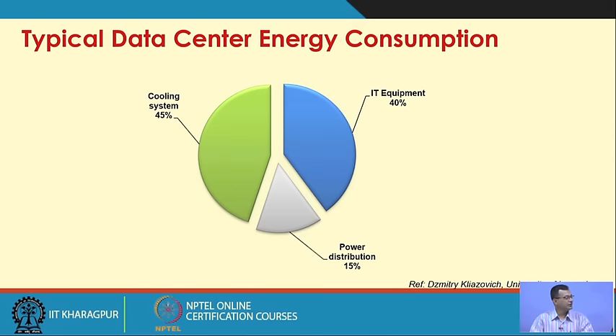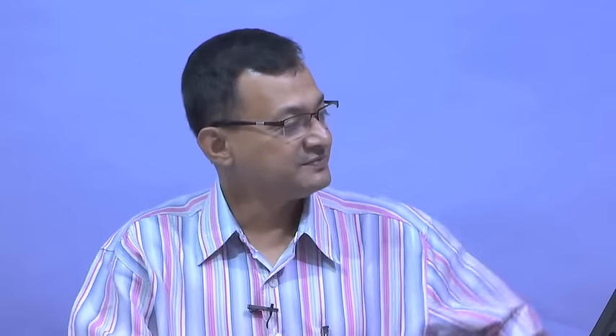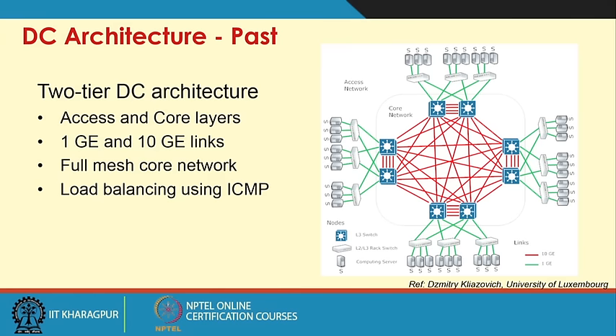Energy accounts for ten percent of data center operational cost today and can rise to fifty percent in the next few years. The cooling system costs around two to five million dollars per year. Looking at a rough breakdown: computing equipment takes around forty percent of power, power distribution takes around fifteen percent, and the cooling system takes around forty-five percent. So sixty percent of energy is consumed by the infrastructure itself, while computing is only around forty percent.